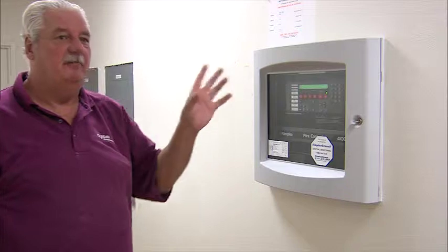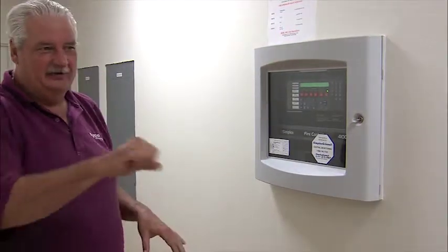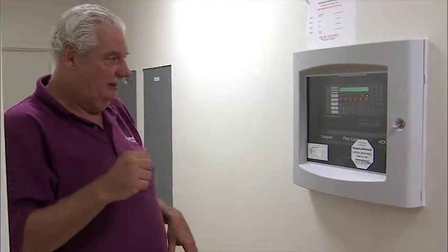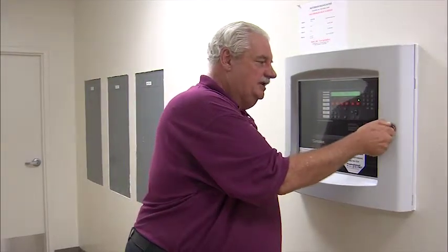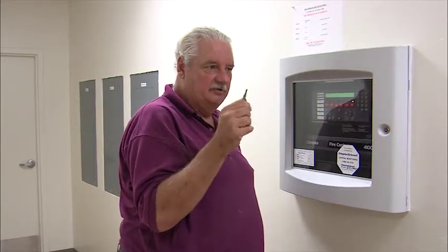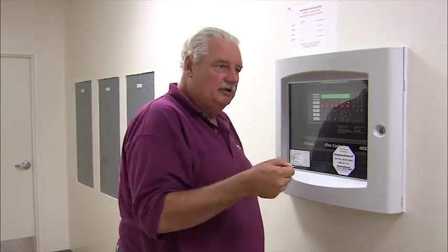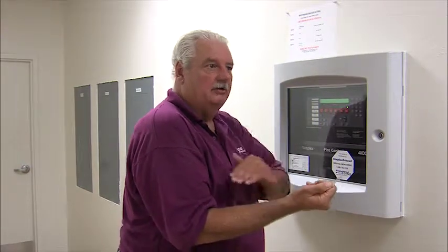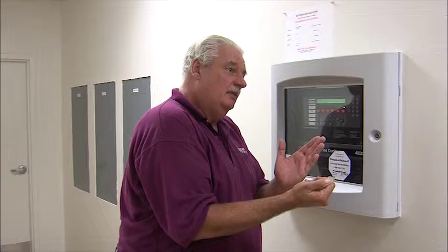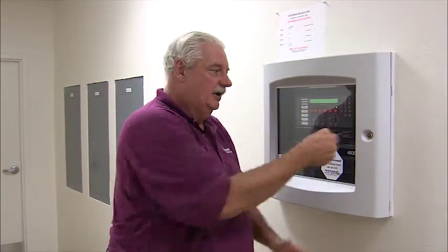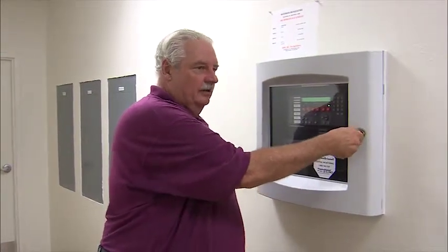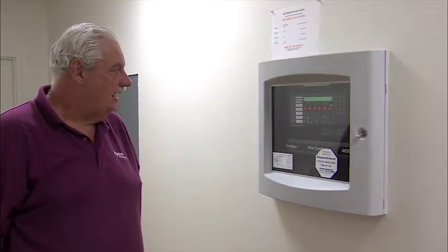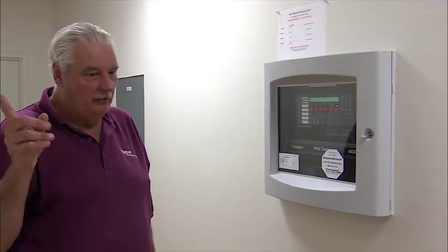So if somebody pulls a pull station, the lever's going to be down. There's a little handle on it. And this key fits all the pull stations too, and we can get you a couple extra keys. What you have to do is just put this in the pull station, turn it, you'll hear the handle snap up, and then you just put it to the wall again and turn it the other way so it's locked. I don't want to do that because I don't want to sound the horns. That's that. We can go over to the pre-action panel.